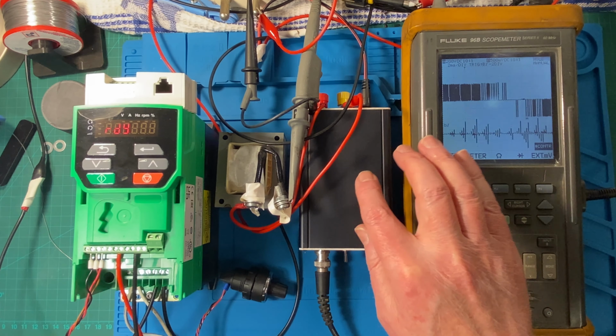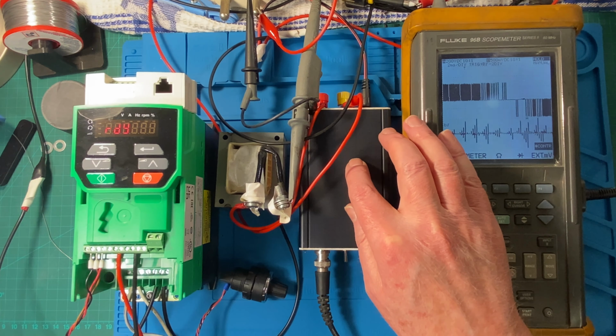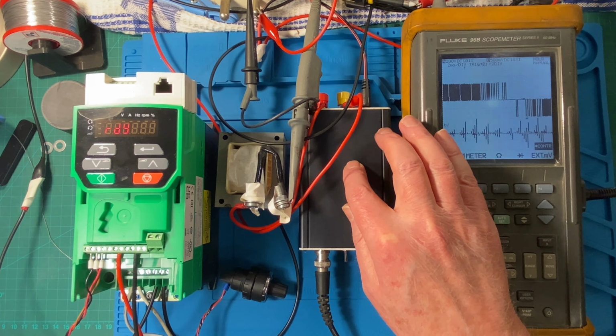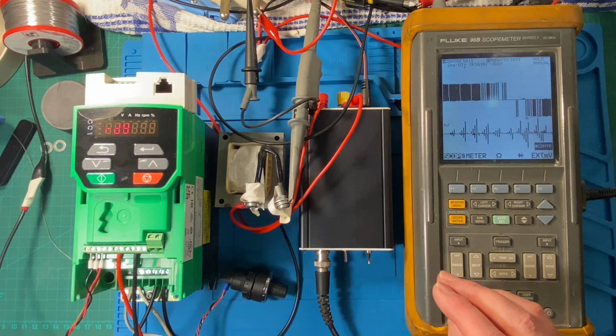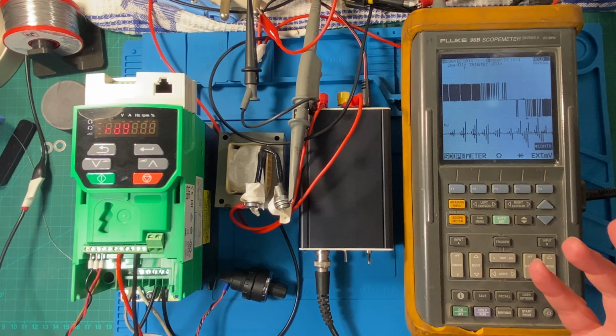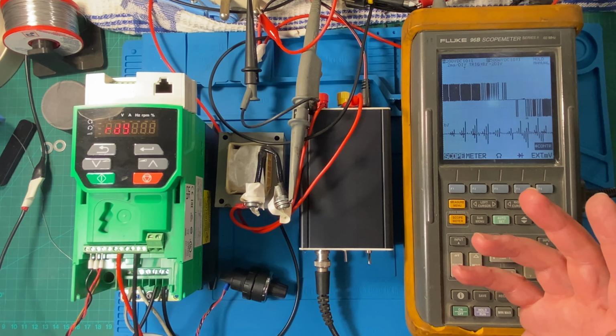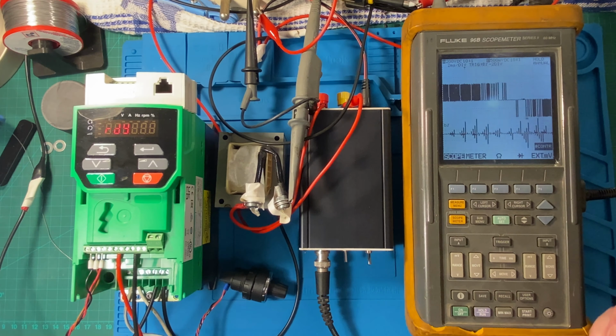This is fast, a 200 kHz bandwidth current transducer, and it's isolated. I would put this onto my storage scope, but I need a high voltage channel and I don't have an isolated differential probe with me. That's why we're having to stick with this scope, because it can handle 2 kV and it's got isolated inputs. So despite it being an old scope which I dug out the trash, it's got a cracked screen and a dead battery, it's still very useful.